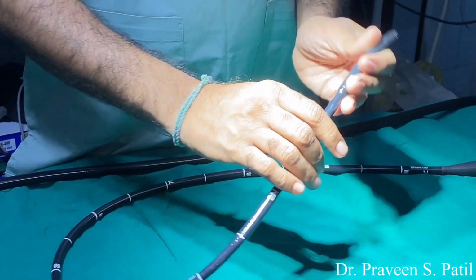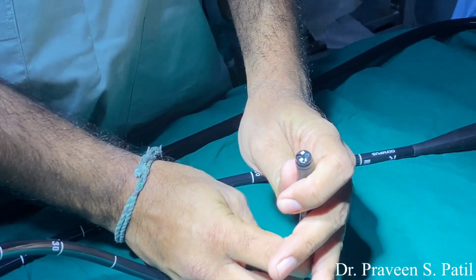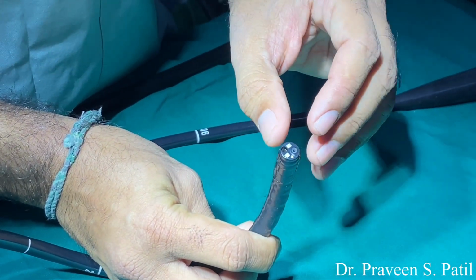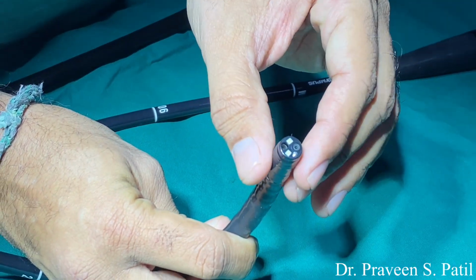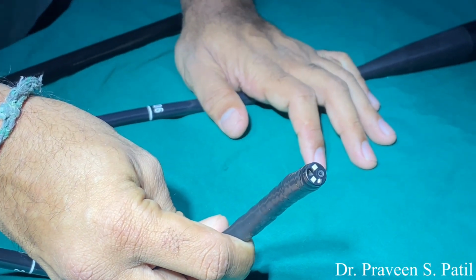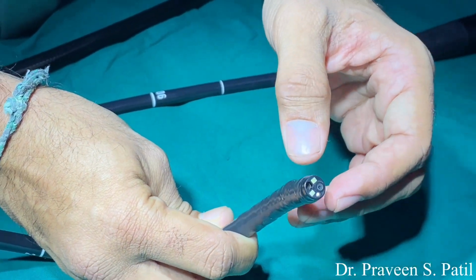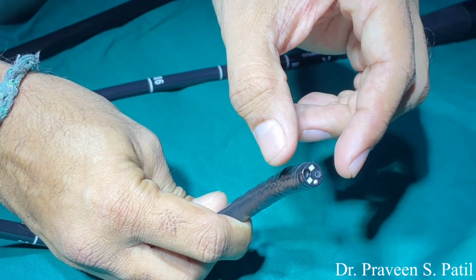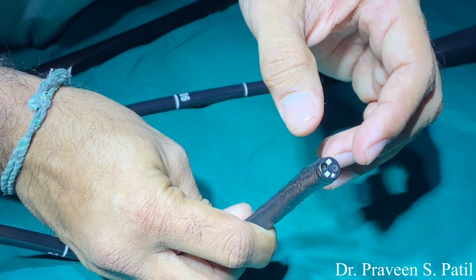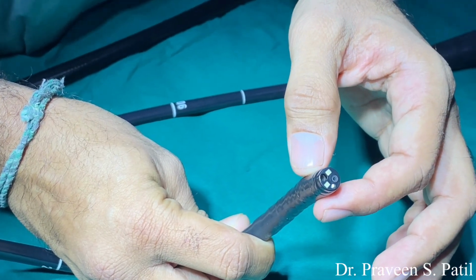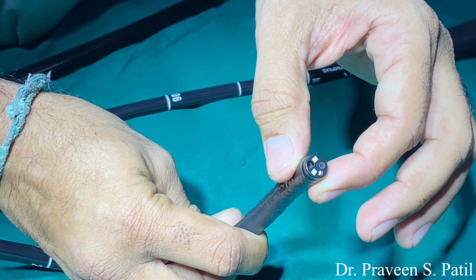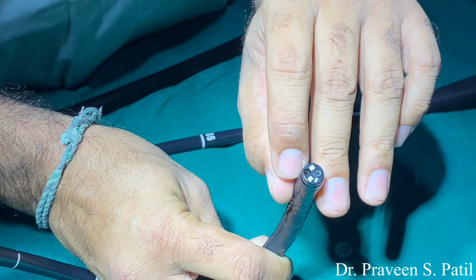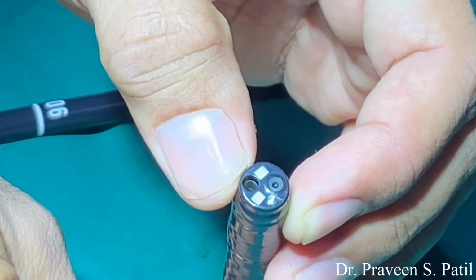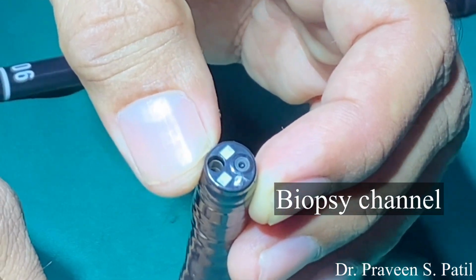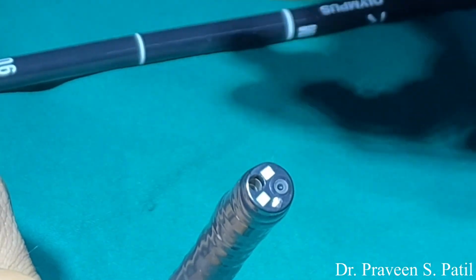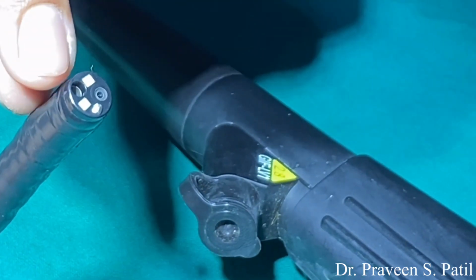Let us look into the parts of the scope, the tip of the scope here. As I told, for diagnosis this is the end viewing lens. Sometimes for ERCP and all, we get side viewing cameras. So this is the end viewing camera. The size of the scope varies from 6 mm to 11 mm. In the 11 mm scopes we get 2 operating openings. Here we have only 1 operating opening. This is for the biopsy forceps, and if you want to push a larger amount of water, you can push it from here and it comes through this opening.